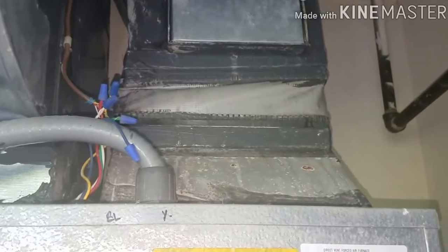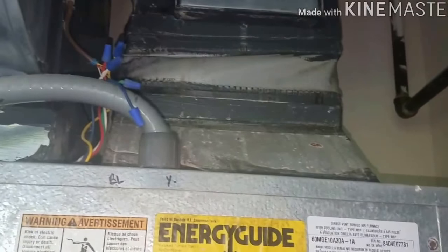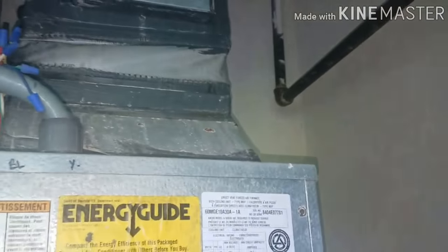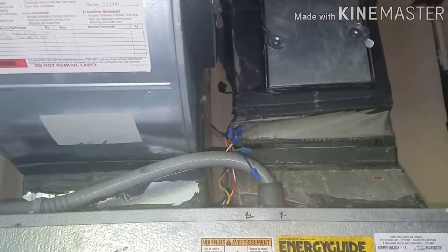Another thing that happens is sometimes when they shut and the heat continues to run on a supply, the ductwork gets so hot. This has been rare, but it has happened - it got so hot it broke the sprinkler system on the 3rd floor and flooded the 2 units below it, so they had to replace 3 units because of one of the dampers breaking and overheating.